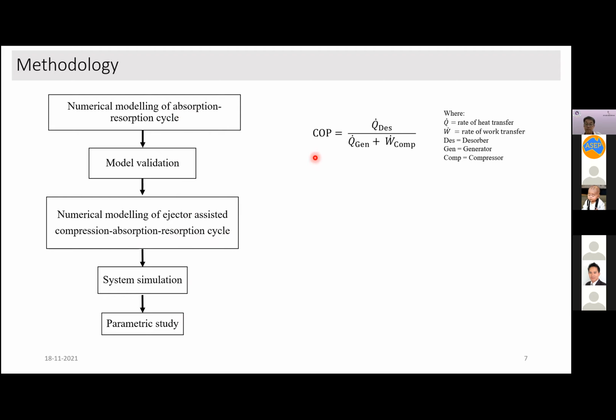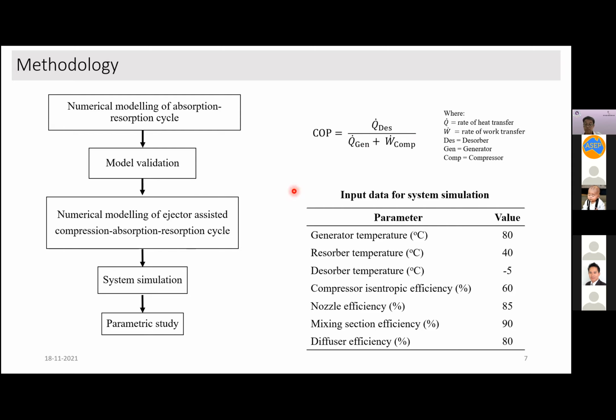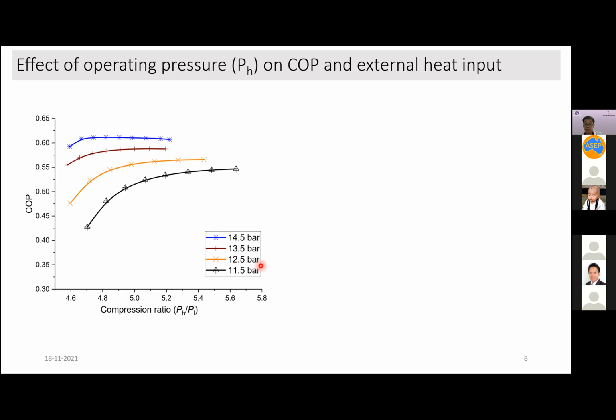The COP of our system is defined as the refrigerating effect divided by the heat input to the generator plus the compression work. The input values for the simulation are adopted as follows. Generator temperature was set as 80 degrees Celsius. Resorber temperature, which is also equal to the absorber temperature, was also set as 40 degrees Celsius. The desorber temperature is -5. Compressor isentropic efficiency was set as 60%. The nozzle efficiency, mixing section efficiency, and diffuser efficiency of the ejector are taken as 85%, 90%, and 80% respectively. So the results of our research are as follows.